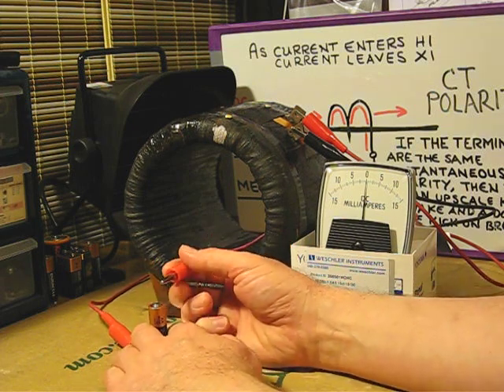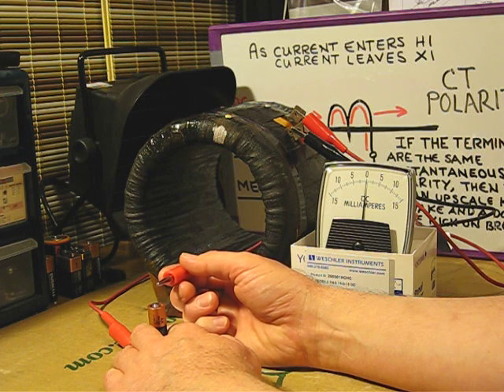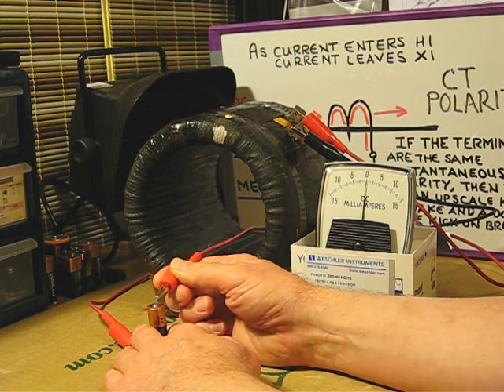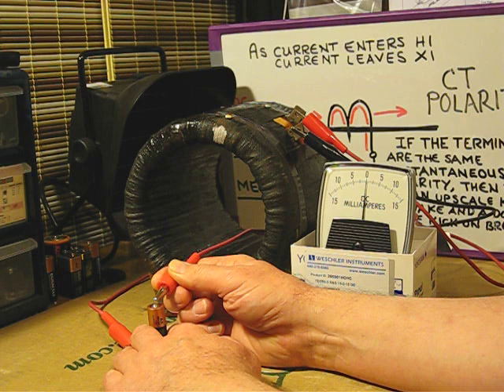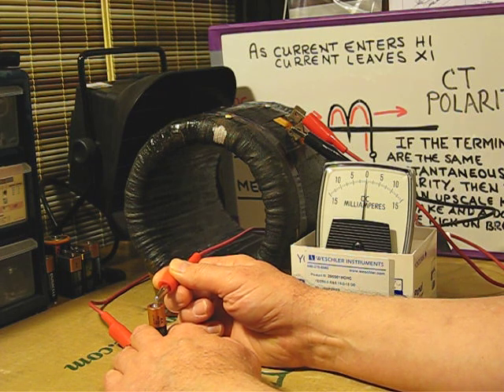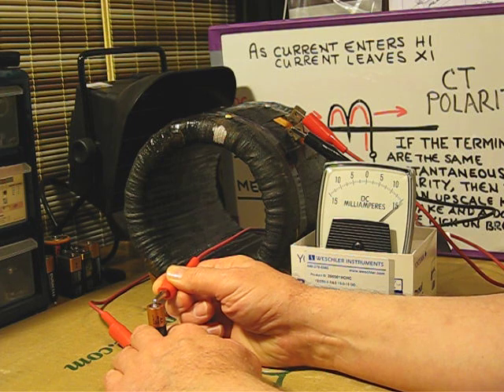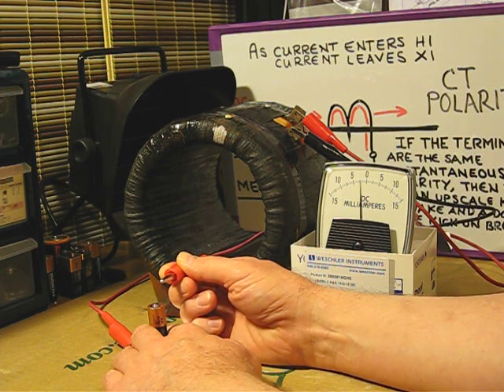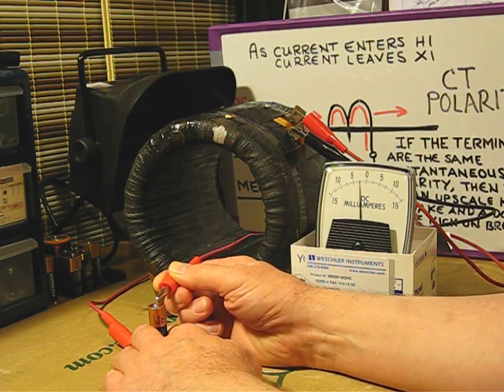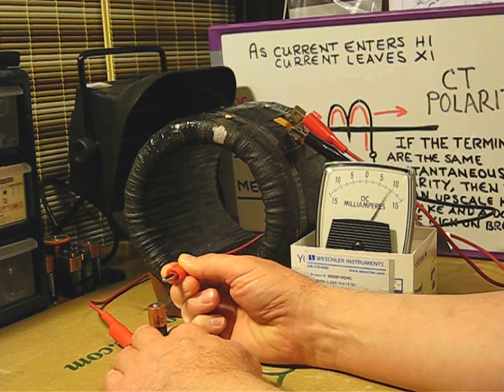Now, since my meter is connected with a positive lead to X1, when I send a positive pulse into H1, I'll see an upscale kick when I make the circuit and a downscale kick when I break the circuit. Upscale on make, downscale on break.